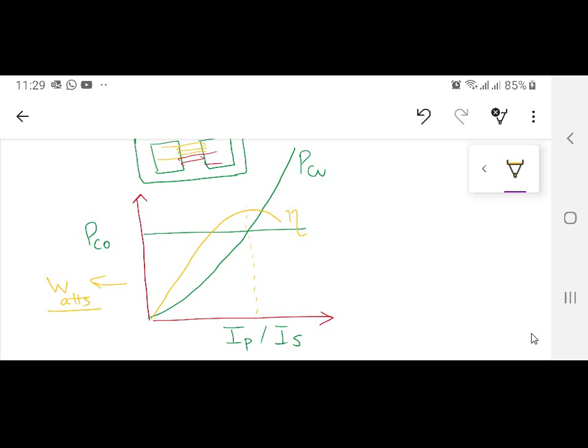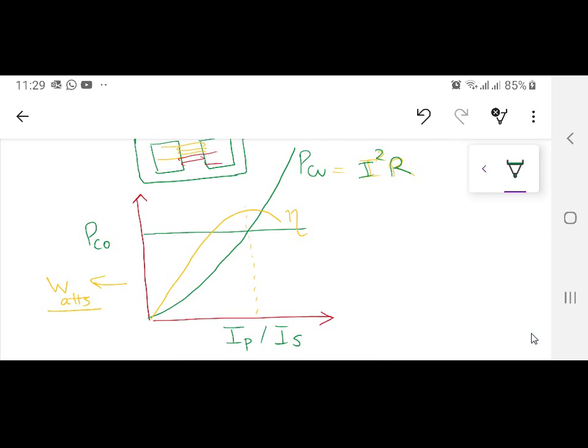The green color curve is the copper losses, and since copper losses are equal to I square R, as current is increasing, you can see it's an exponential increase over there. Now a point comes when these two curves are crossing each other. That point is when the copper losses are equal to the core losses. This is the point of maximum efficiency of your transformer.